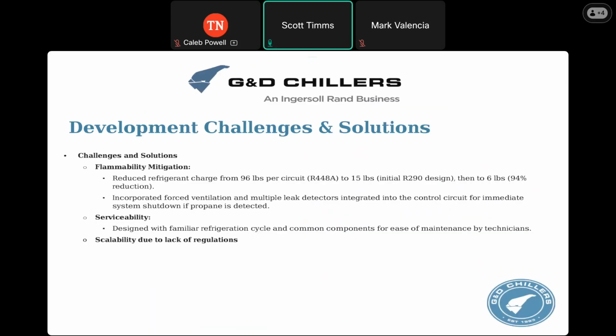So essentially, yeah, the main issue with propane is that it can light on fire, right? So CO2 requires really, really high pressure, so there are some safety things around that. And then obviously on the propane side, there's flammability issues. So we had to come up with some solutions to make these systems safe, right? So prime directive there is to make sure everything is safe. So the first thing that we did was reduce the refrigerant charge. So if there's less propane in the system, then there's less flammable potential, right?